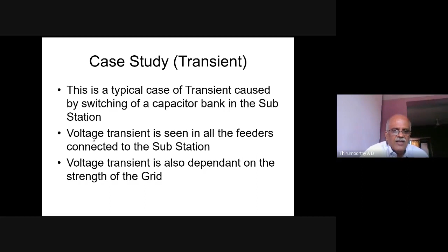You can see that the voltage transient, whenever the capacitor bank is switched on, is very sharp. These kinds of repetitive transients have an impact. This transient was recorded in a customer facility which was 2 kilometers away from the substation. So that is the kind of transient that can impact the consumer when the capacitor banks are switched at the substation. Repetitive transients like this impact customer installations, transformer bushings, transformer installations, motor installations. All these installations will get prematurely aged, and one day one may fail under a severe transient. So transients are very important and must be managed.